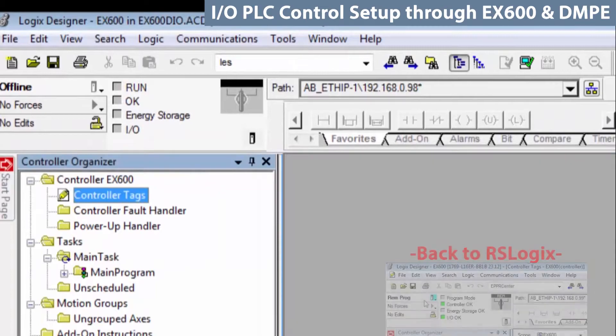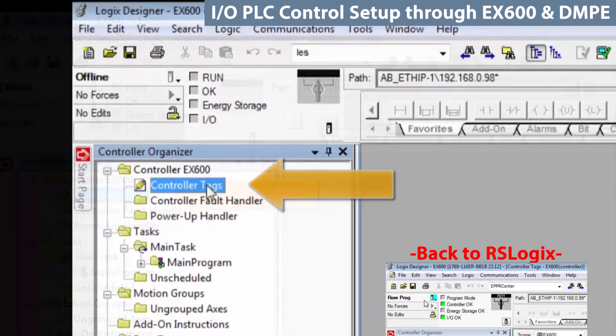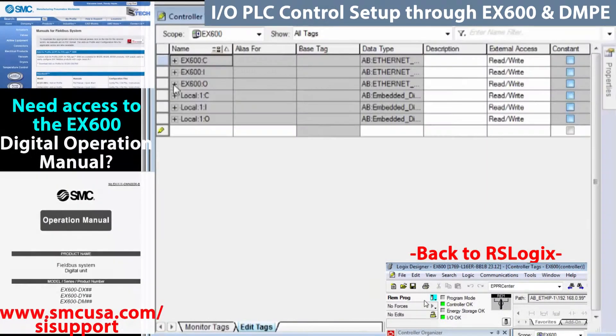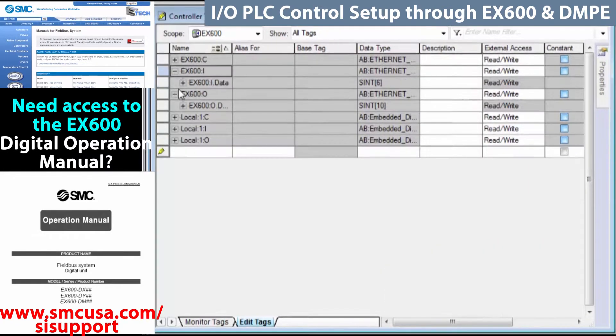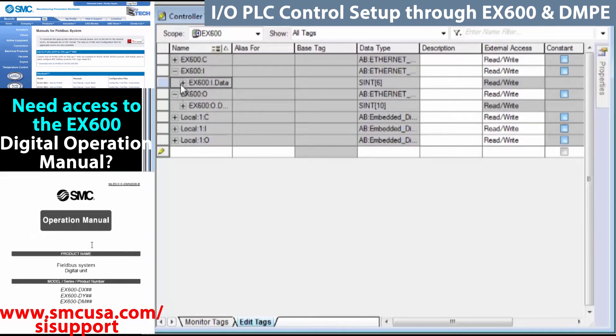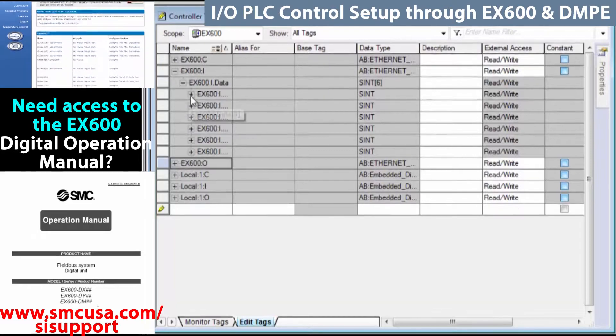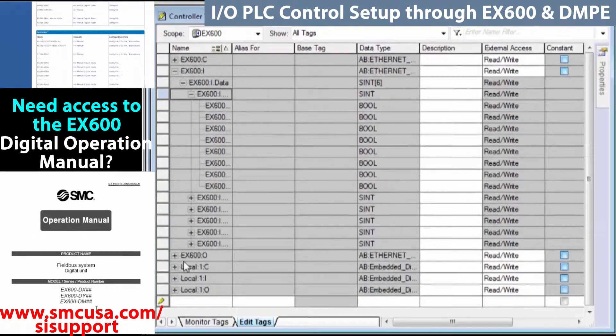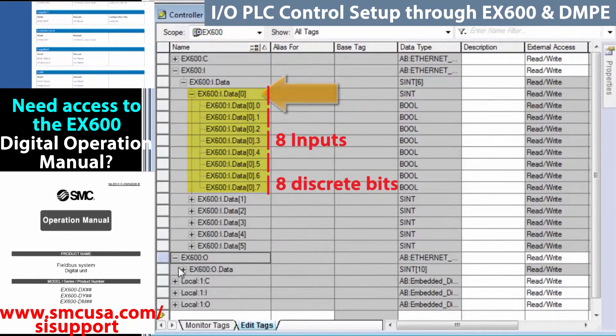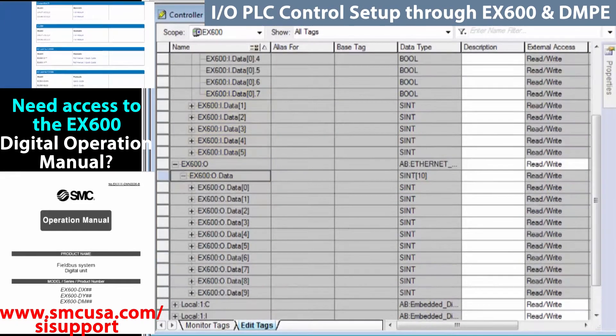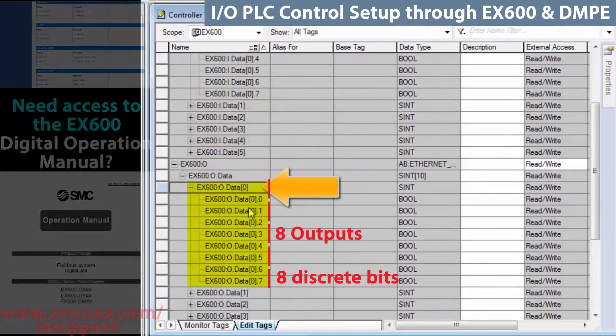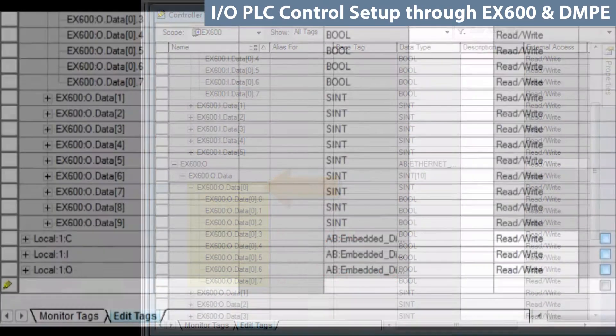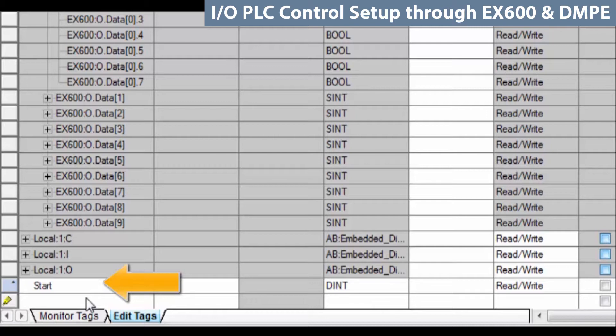Open up the PLC program and if you go to controller tags, you will see that we already have our data mapped for the EX600. Specifically, we're dealing with the digital inputs and outputs. Those are going to be the first byte of input and output. That's actually these bits here and these bits up here. So now, we will first create aliases for the inputs and map the solenoid bits to match.